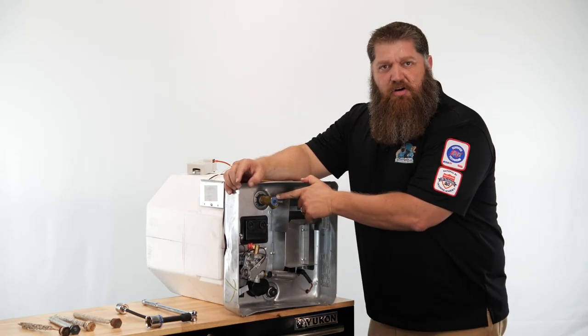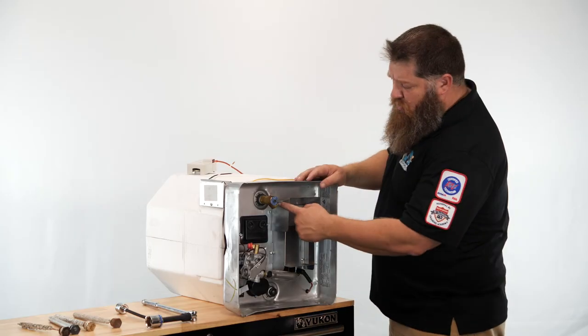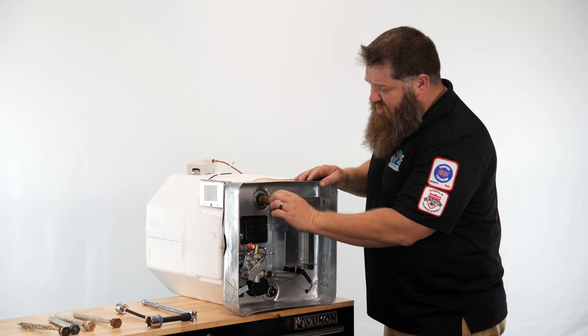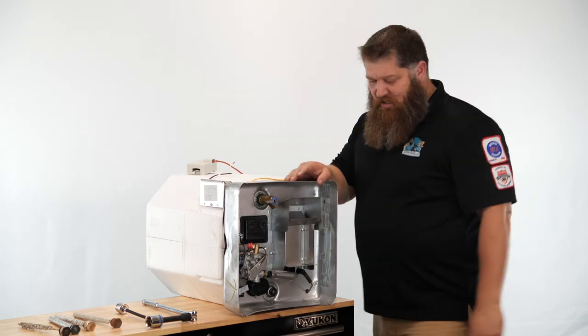Now that we have it installed, we'll actually turn on the water. We're going to leave, very important, we're actually going to leave our pressure and temperature valve open. Cold water is coming in, beginning to fill up our tank. And then, once water starts coming out of our pressure and temperature valve, we can simply close it. Go ahead and dry off just a little bit.